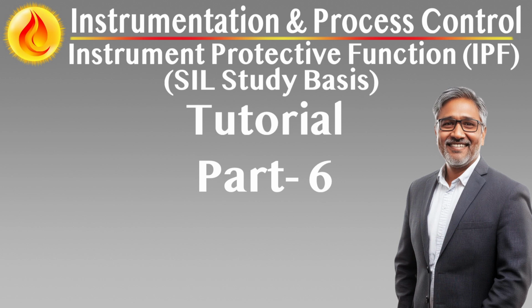Emergency Shutdown Systems, ESD, Fire and Gas Systems, FGS, Alarm Management Platforms, and Asset Management Systems for visibility, coordination, diagnostics, and event logging. However, this communication must be managed with strict boundaries to ensure that integration does not compromise the independence, reliability, or safety integrity level (SIL) of the IPF. Interfaces must be carefully defined, validated, and secured to maintain both operational functionality and safety performance.